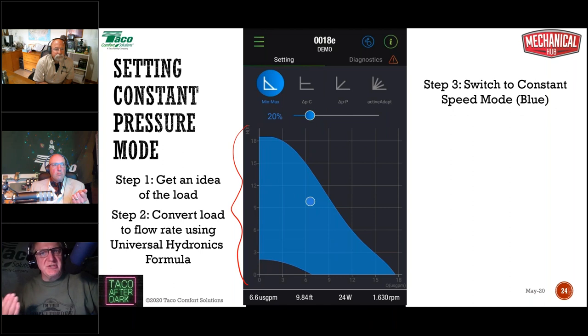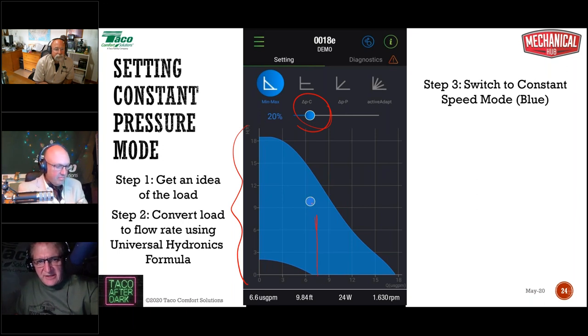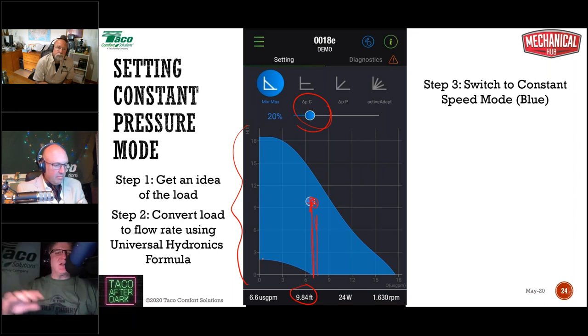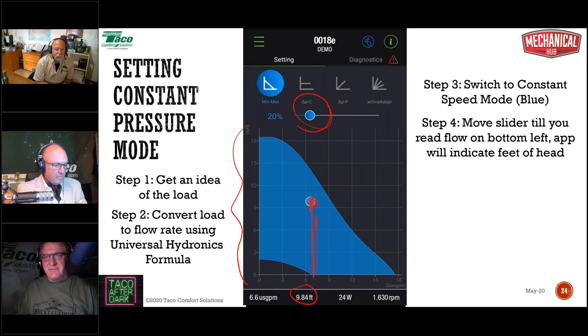Then I'll switch to the blue mode, the constant speed mode, and I'll adjust this dial until this dot is on 7 gallons a minute. So let's say it's at 7 gallons a minute right there. Down below, it's going to tell me what the head loss really is. So when using this pump, all I need to know is the flow. If I get an idea of the flow, it'll figure out the head for me and I can program it accordingly. So I can move that to 7 gallons a minute, and it's going to tell me the head.